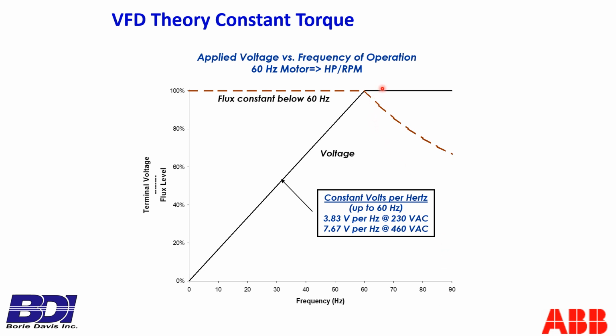Some balance, they do the test and balance and find out, if I could just get another 10% flow out of this thing, everybody would be happy. Well, if you look at the reality of what's happening at 60 hertz, if you are not fully loaded at 60 hertz, i.e. if you're not at 6.7 amps on a 6.7 amp motor, that means you don't need 100% torque to operate. Maybe you're operating right down here right now.